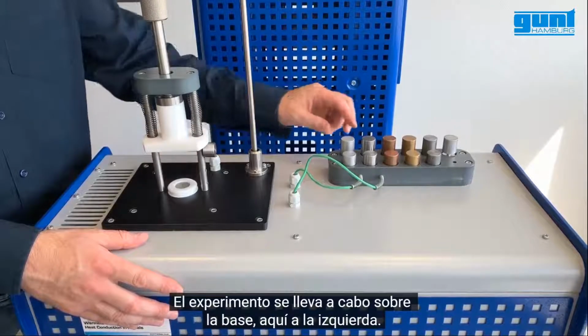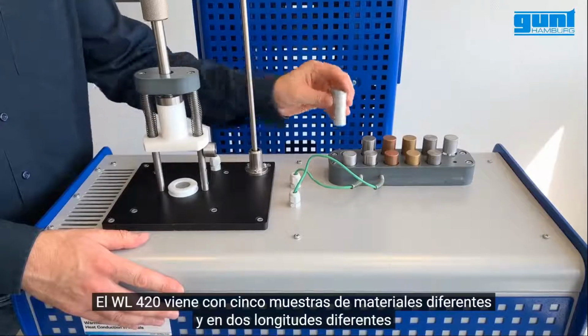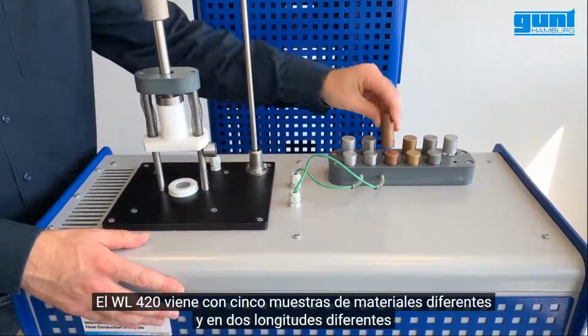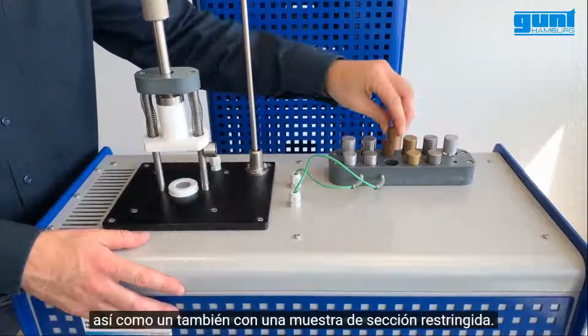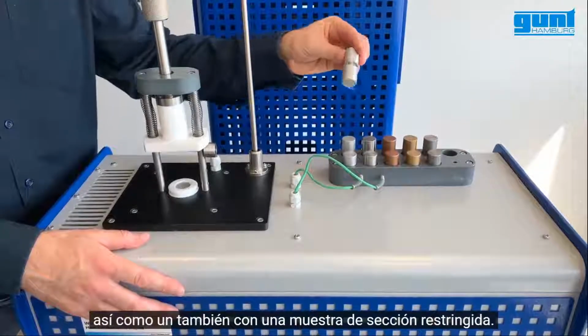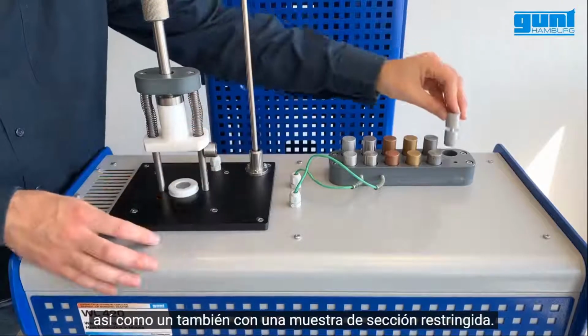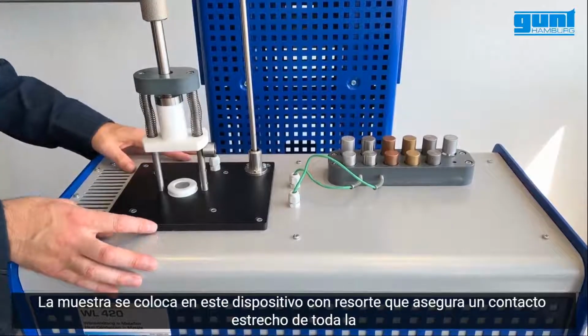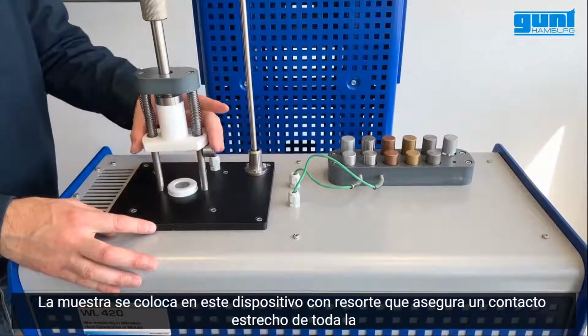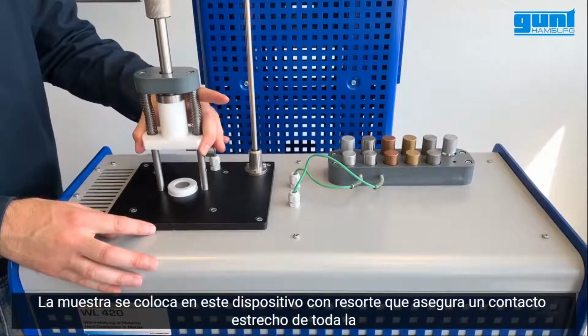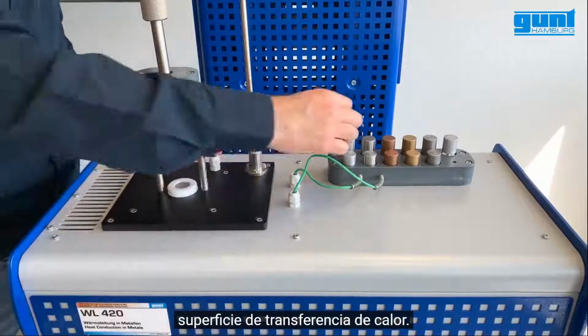The WL420 comes with a specimen for 5 different materials in 2 different lengths respectively, as well as one specimen with constricted cross-section. The specimen is placed in this spring-loaded device, which ensures reliable contact of all heat transferring surfaces.